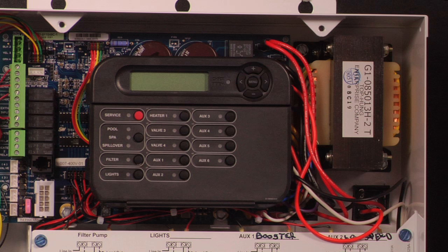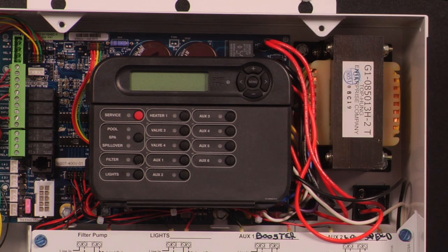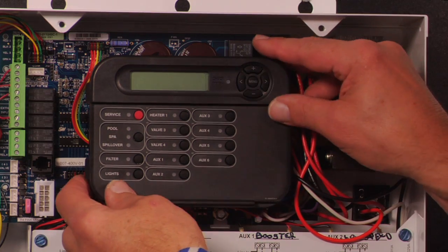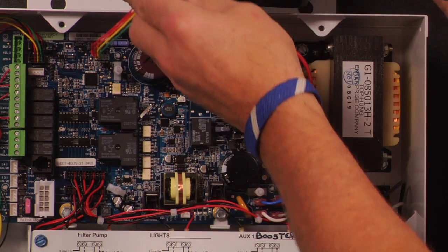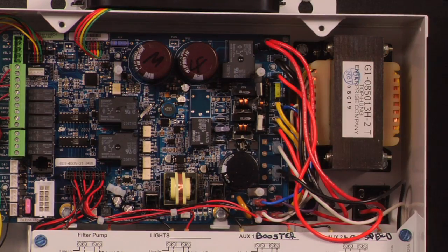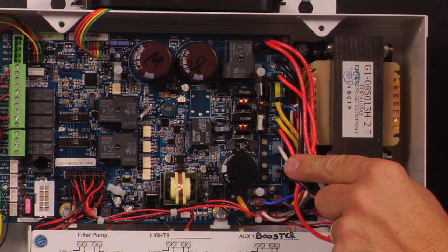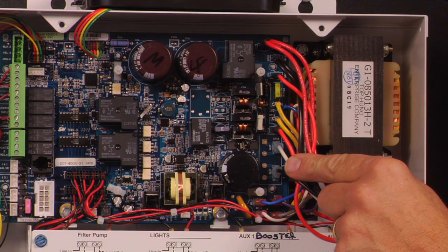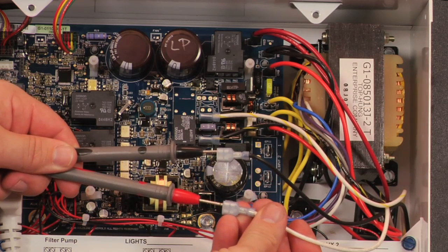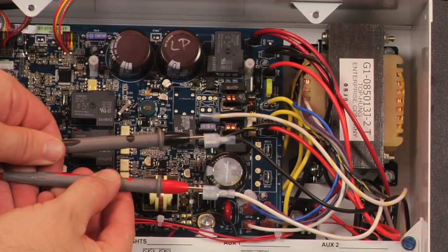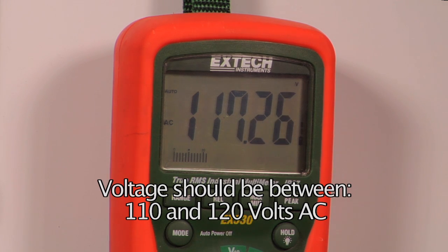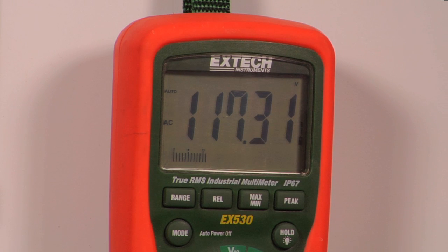A blank local display or no LEDs is caused by either a bad display or no voltage to the display from the main board. Remove the local display from the main board. Remove black and white wires from the lower right corner of the main board. Insert the meter leads into the black and white wire connectors. The reading should be 110 to 120 VAC. If there is no voltage, verify that the circuit breaker used to power the ProLogic is in the on position.